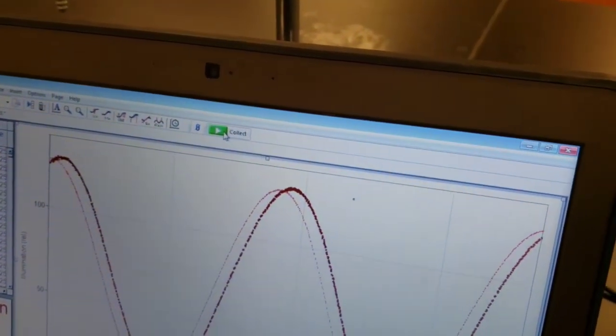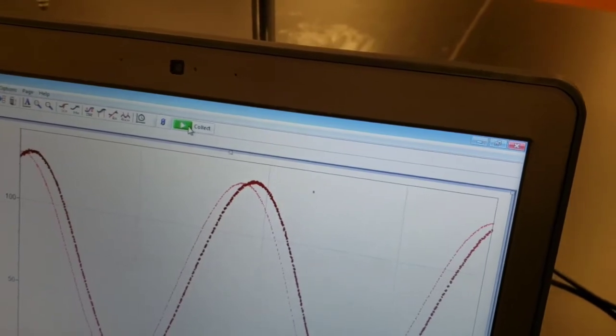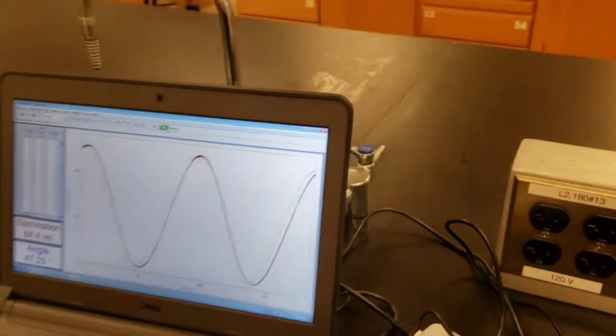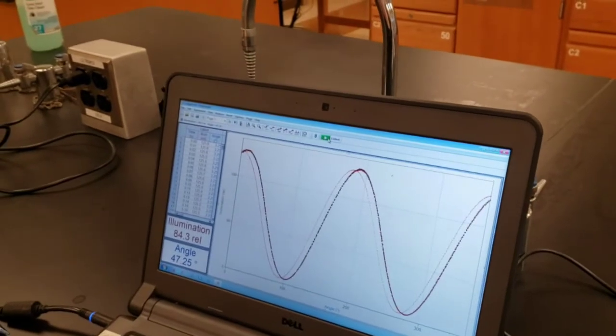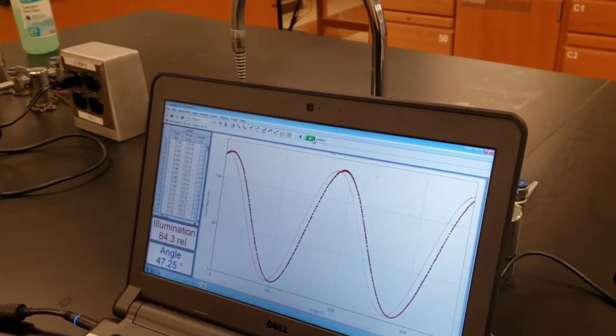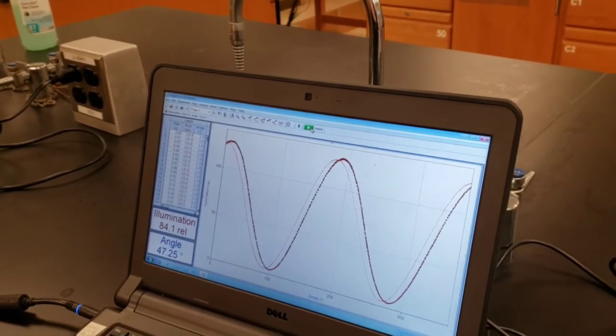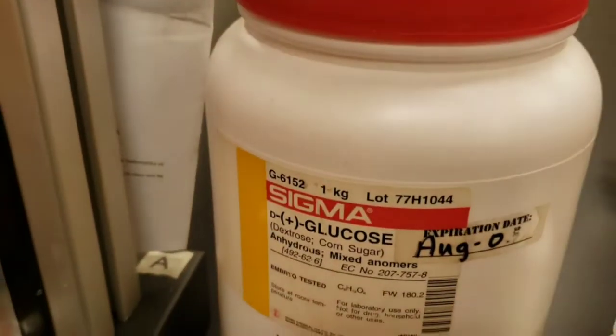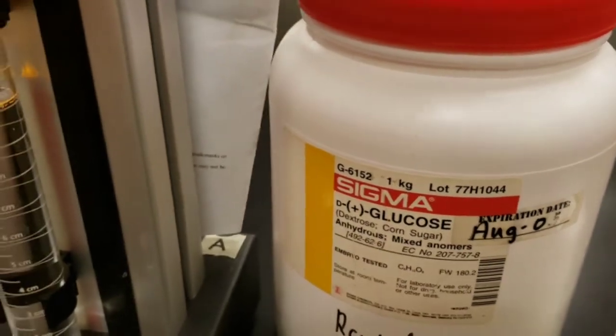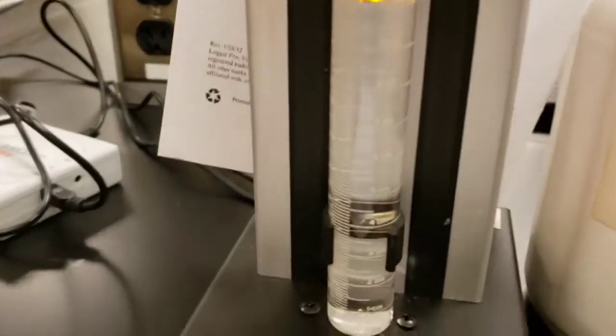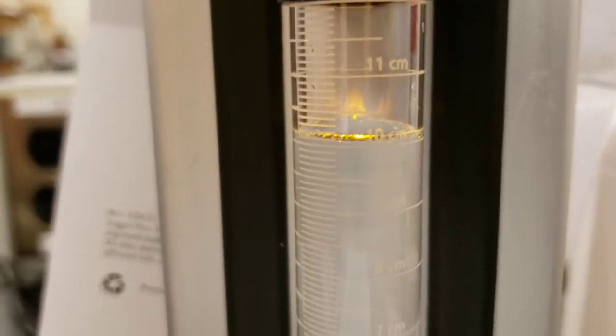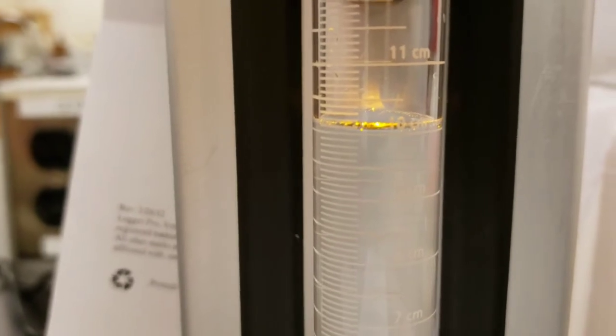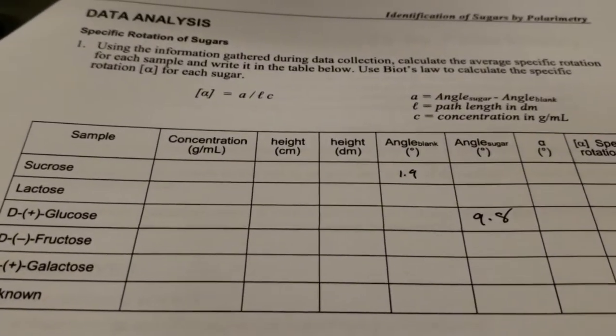This gives a new trace that is either peaking to the left or peaking to the right of the calibration curve. Record the angle of maximum illumination for this particular sample. This one was D plus glucose. For each sample that is run, it's important that you measure the height of the meniscus in the sample cell holder. This has to be reported in the data sheet.